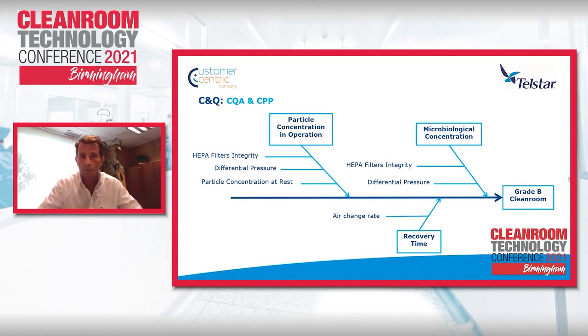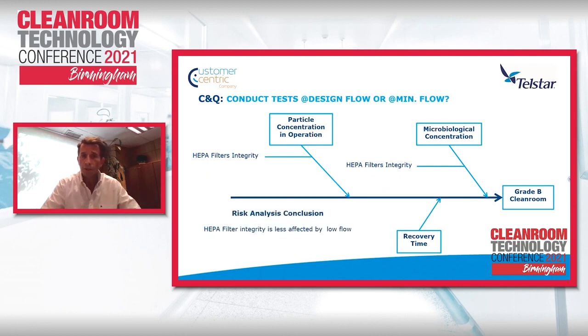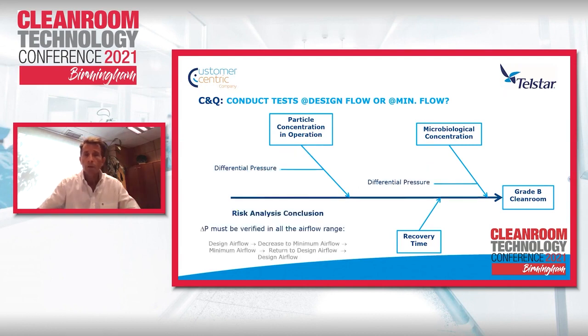For the qualification part, we made the risk analysis on the critical quality attributes, which are the particle count, the microbial concentration, and the recovery time, and on which critical process parameters affect these attributes. Considering the HEPA filter integrity, the conclusion is that the scenario where HEPA filter integrity is more compromised is the conventional scenario. In eco mode, we will have lower flow and the integrity risk of the filter will be lower. If we talk about the differential pressure, the conclusion is that we have to check it at the different scenarios, not only at the conventional or at the minimum flow, but on both and the transition periods.